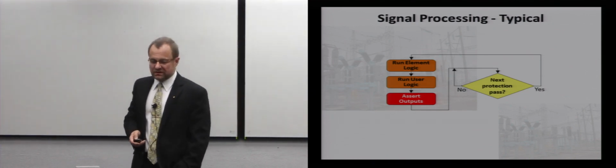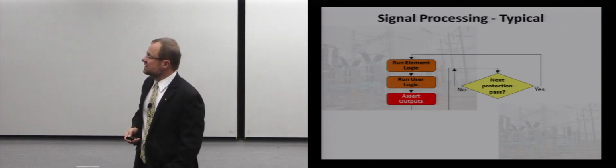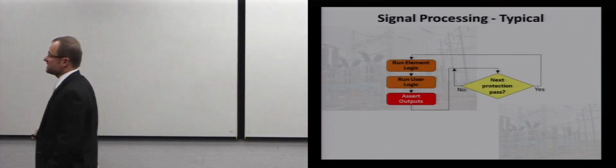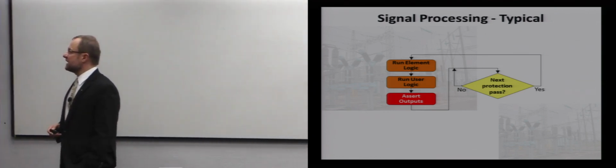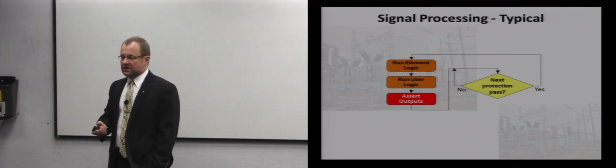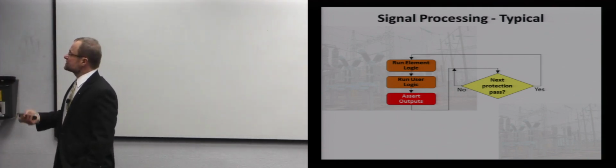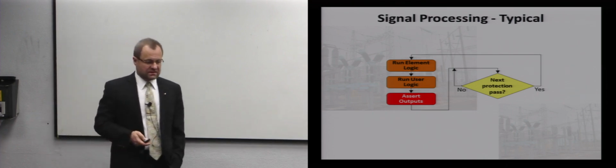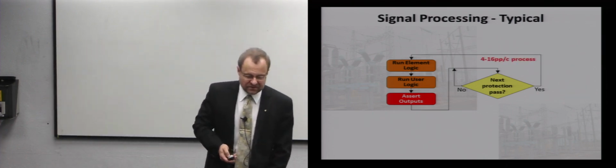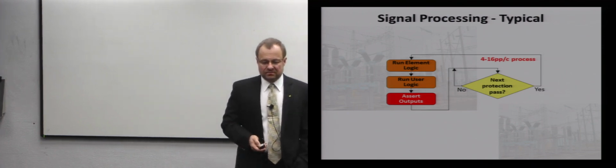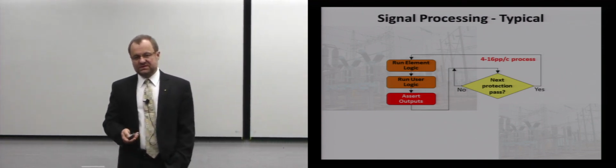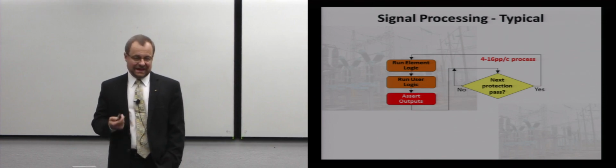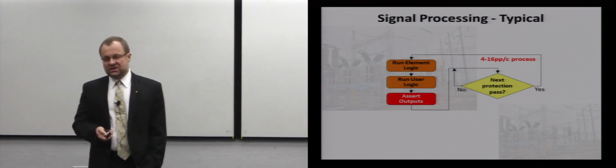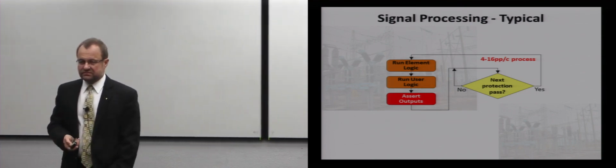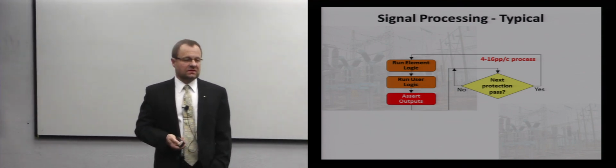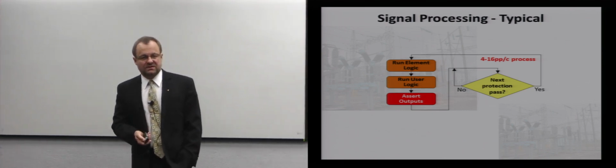And then the last one is the final decision making, meaning that we run the element logic. We check our IZ minus V angle against something else. If there is a timer, we time out. We run user logic, and we assert outputs. And this is typically done 4 to 16 PP over C. And PP stands for protection pass or protection scan, meaning that we check whether or not we should trip, make our final decision, say 16 times in a power cycle or 8.